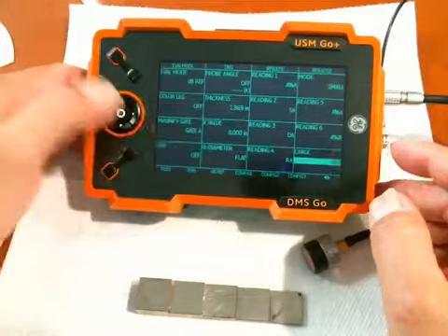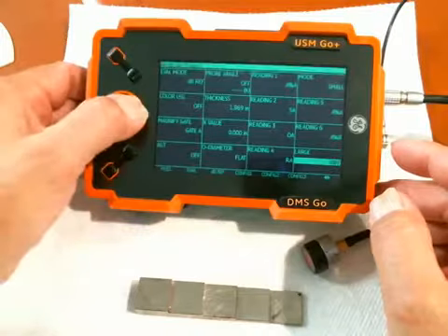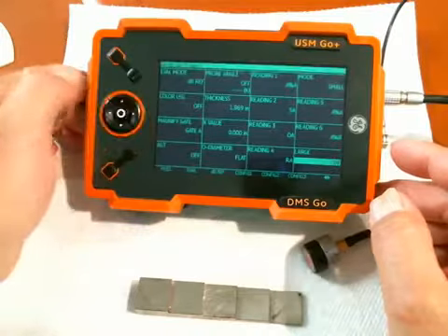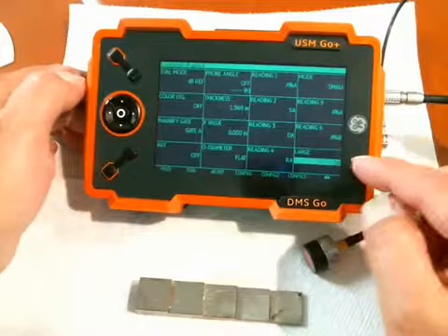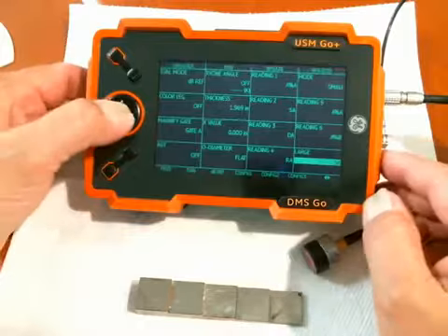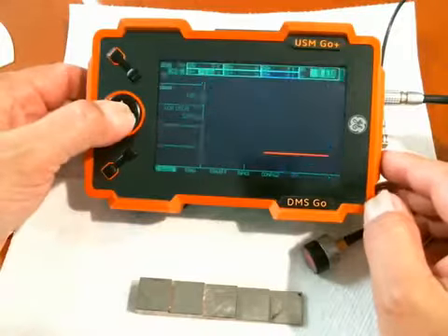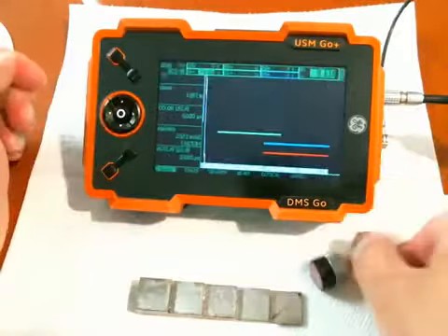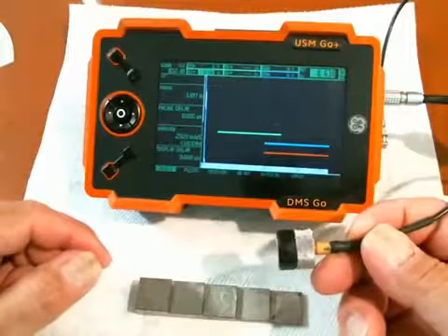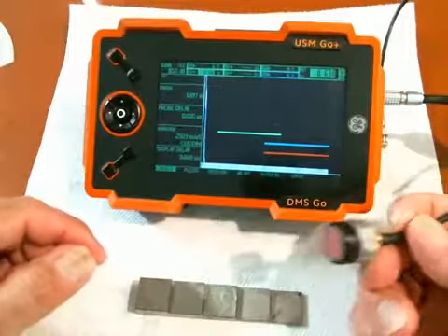And so we'll select that parameter and we will make that SA. Okay, so now the sound path in gate A is going to be our big reading. We'll go back out to the main menu, and now we see that the sound path in gate A is our large reading.